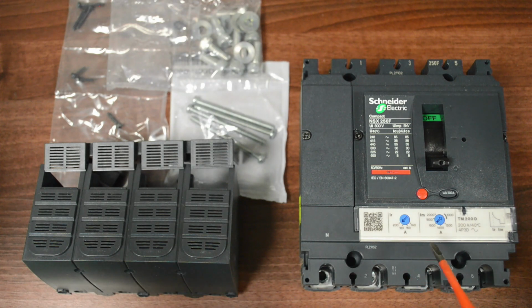You'll see on this particular model you've got IR down here and a little adjustable dial with a scale from 200 down to 140, and you know it's talking about amps because you've got an A underneath there as a clue, and then we've got IM over here, and again we're going 2000 down to 1200, and again it's set as an amp value. And it's just to try and explain a little bit about those and also how these are connected together. So typically you would be fitting lugs onto your cables that are terminated onto these, usually due to the size of them.